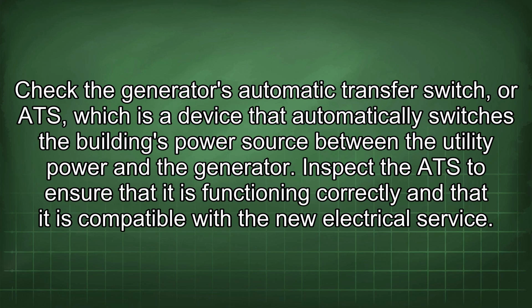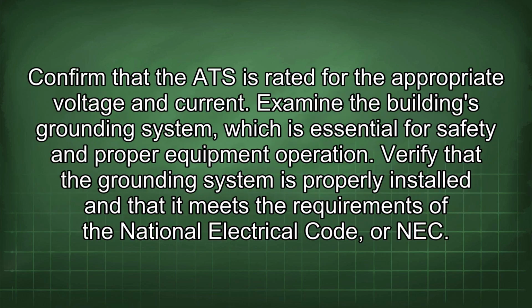Check the generator's automatic transfer switch, or ATS, which is a device that automatically switches the building's power source between the utility power and the generator. Inspect the ATS to ensure that it is functioning correctly and that it is compatible with the new electrical service. Confirm that the ATS is rated for the appropriate voltage and current.